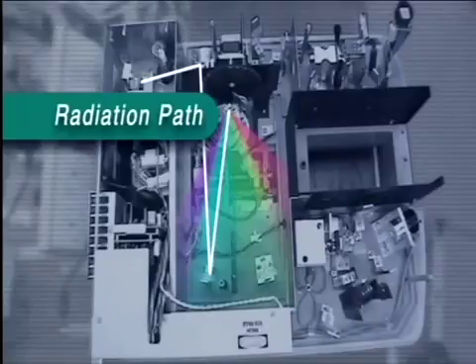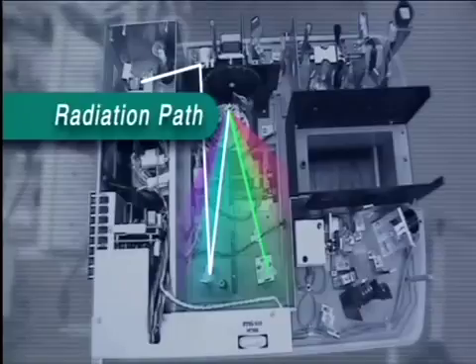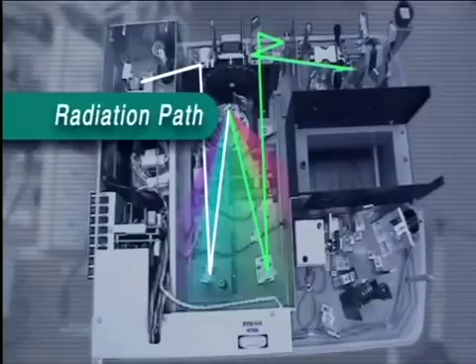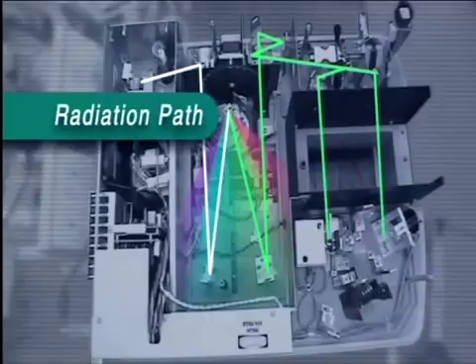A single wavelength passes into the modulator, which consists of a rotor with mirrors on it. This chops the light into two beams. One beam passes through the sample cell, while the other passes through the reference cell. So the instrument is referred to as a double beam instrument.